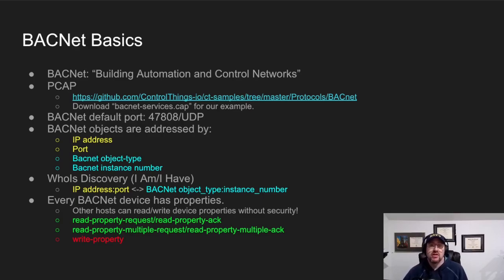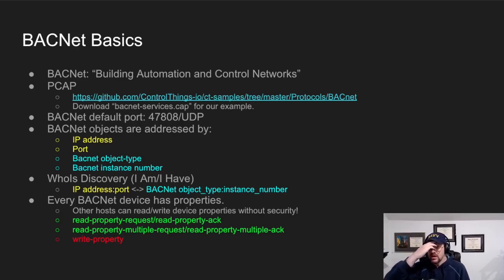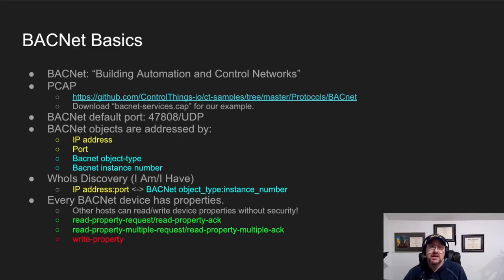For the purposes of this presentation and demo, there is a PCAP out there — I gave you the link. It's public, you can download it. I'm going to use the one titled BACnet-Services.cap. Another piece of information: BACnet's default port is 47808 UDP. It can be on other ports, but 47808 is the one I see it on most often.